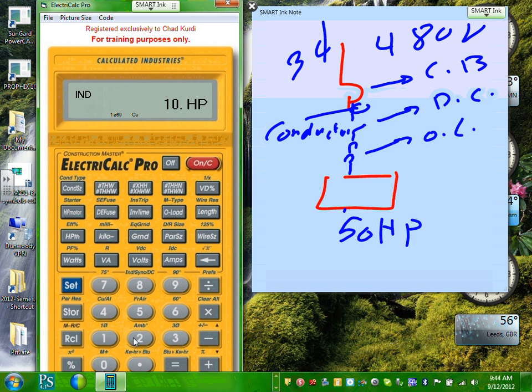So here's my 240 and hit voltage. That's all you need to do. The voltage, 240, hit volt, and 10 hit horsepower. Everybody's done with that? Okay, let's find the full load amp for this one. 50 amps. Just hit amps. Did you guys get 50 amps?